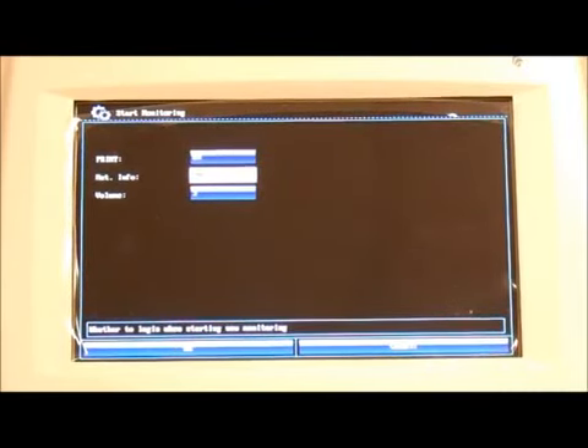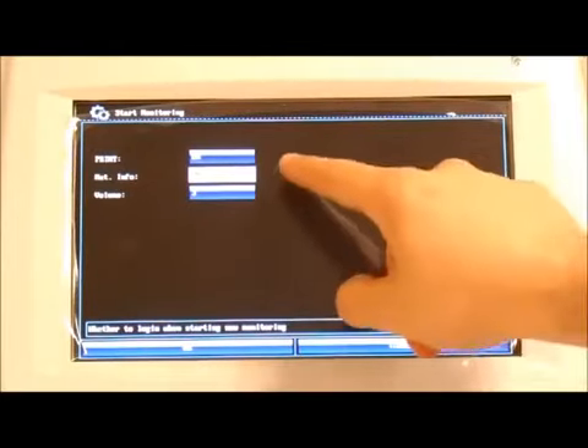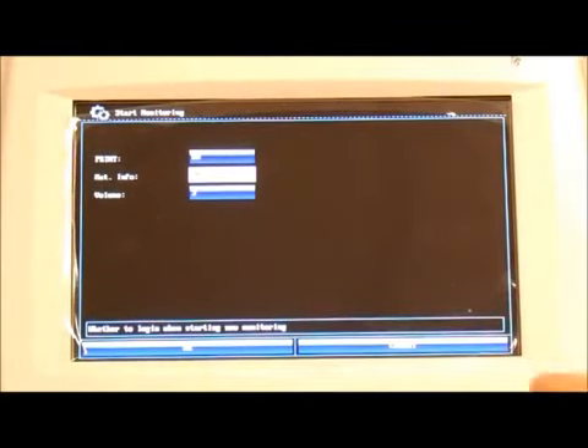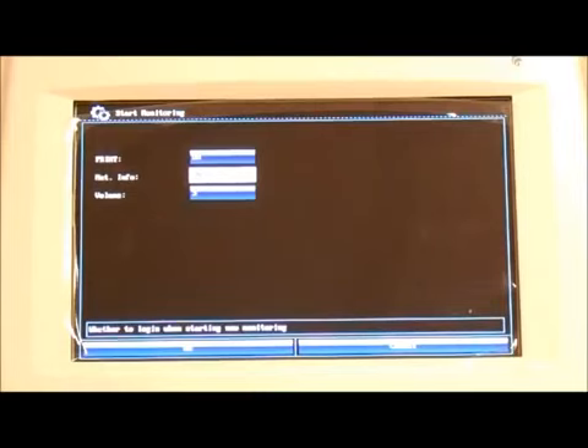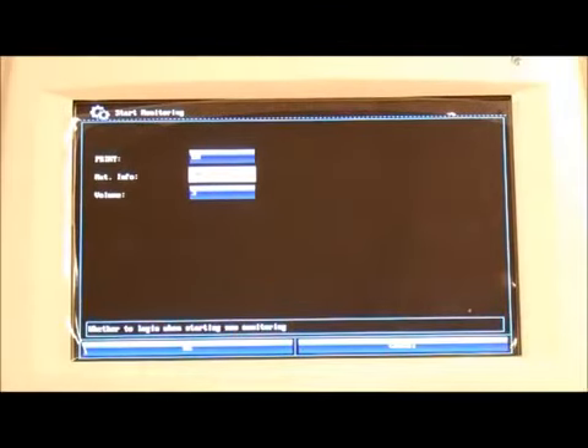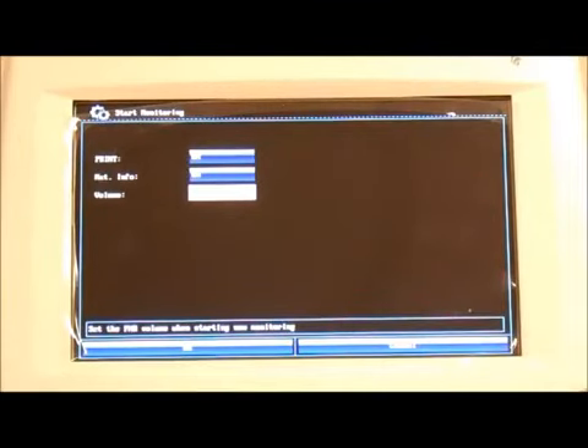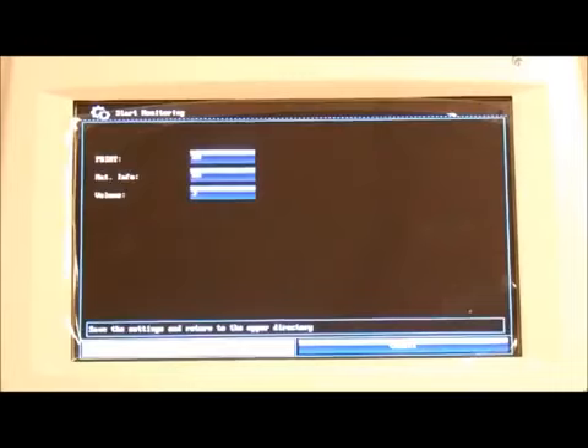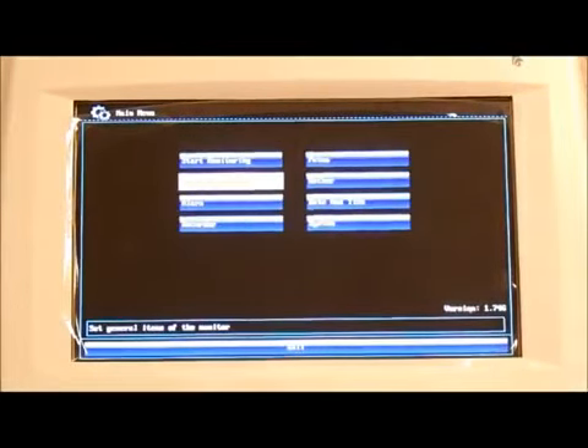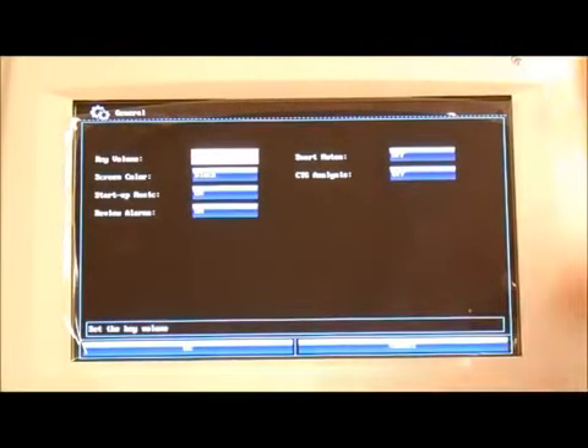So typically the most recommended setting is to have Print on and maternal info on, so that the machine automatically starts printing and it'll remind you to enter the patient information. Because otherwise, at the end of the day, if you have a long strip with no patient information, it may be a little bit hard to identify it. So right now we'll set Print to on, maternal info to on, and volume 3. The volume is the intensity of the FHR feedback. So we press OK.